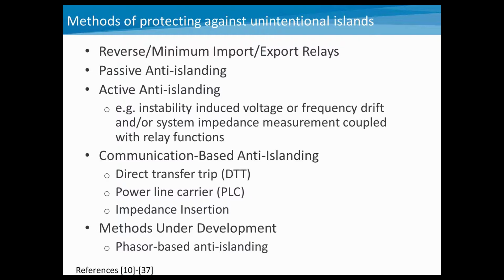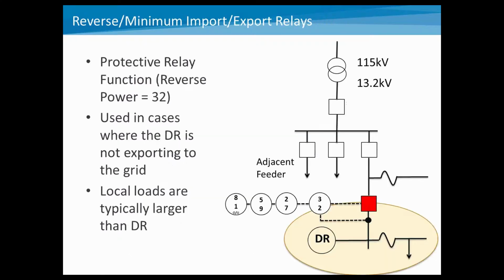So as we move on to additional methods for protecting against unintentional islanding, there's a variety of different types listed here. We'll go through these in more detail. Reverse and minimum import power relays, passive anti-islanding detection methods, active anti-islanding detection methods, communication-based anti-islanding detection methods, and some that are under development. And I'll talk a little bit about each of these. But if you take a look at references 10 through 37 in the back, there's a lot of information available on a variety of different anti-islanding techniques. I would recommend browsing through these references if you're interested in more details on any one of them.